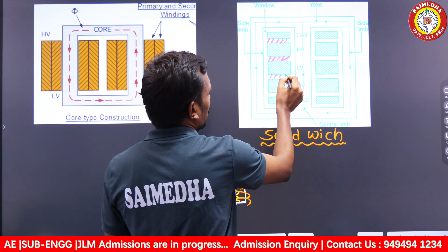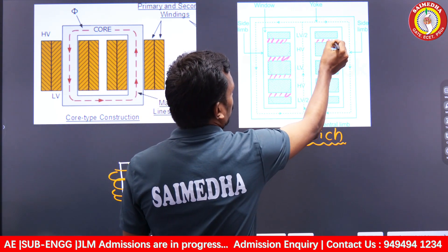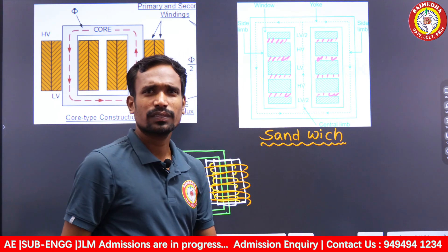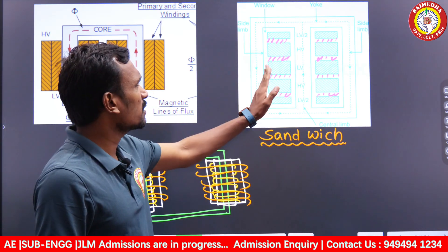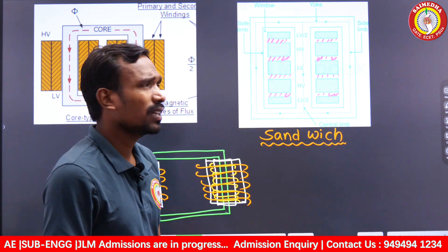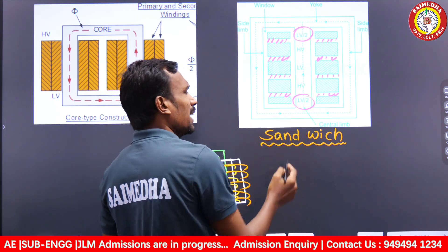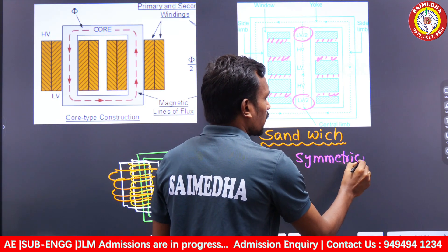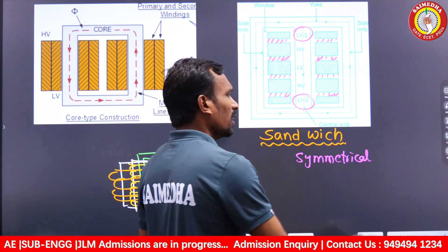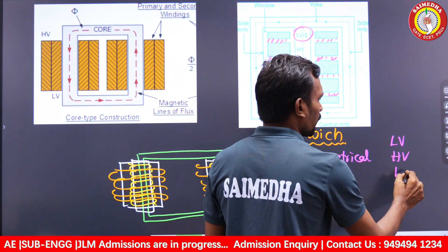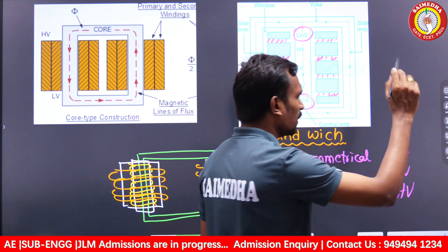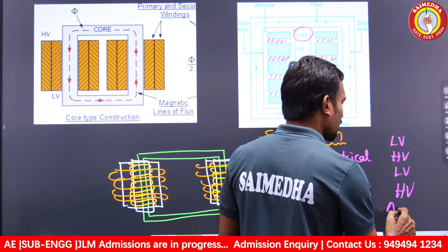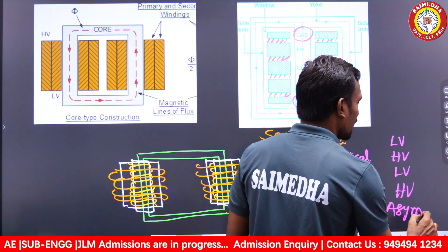Insulation is placed between every winding layer. If the top and bottom layers are the same — for example both LV — that is called symmetrical sandwich winding. If the top layer is LV and the bottom layer is HV, that is called asymmetrical sandwich winding.